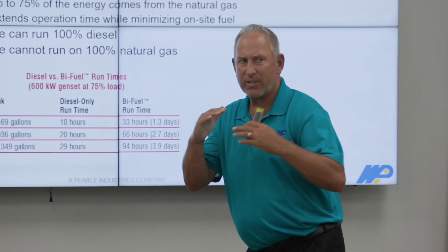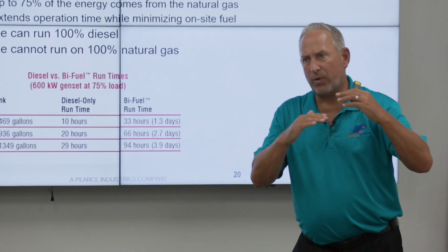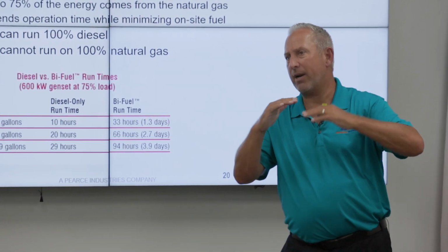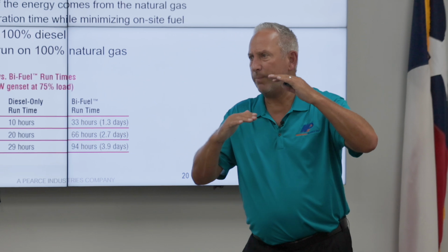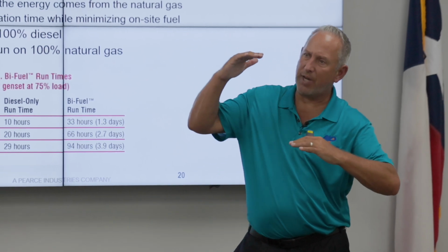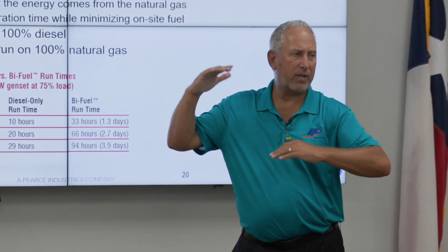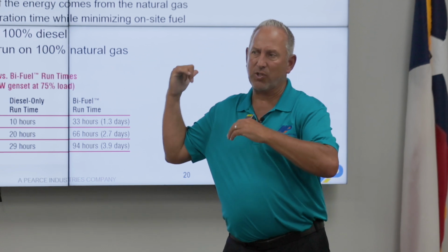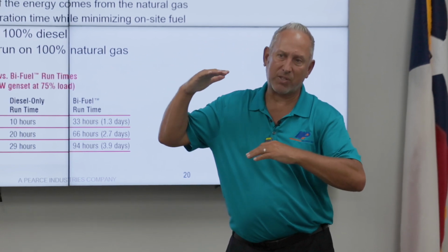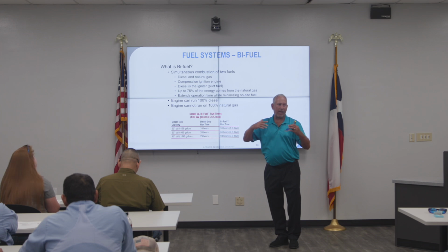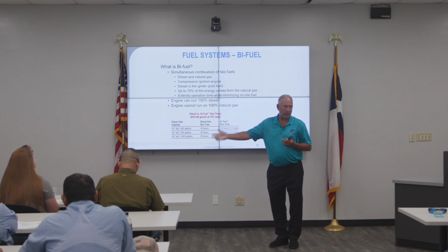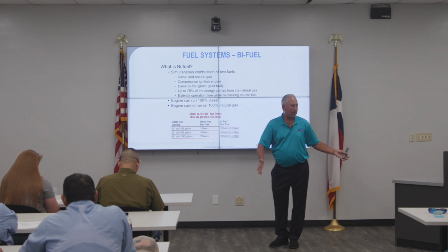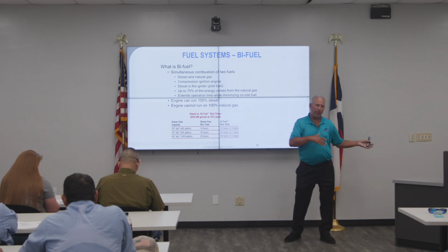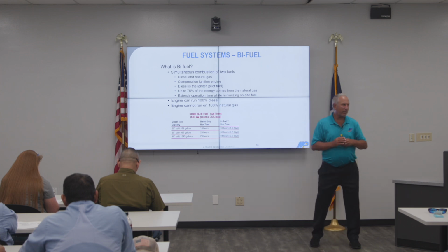Now, when you start running more on natural gas and less on diesel, your particulate matter goes down, but because you're doing natural gas, your NOx goes up. So what Generac does is they put a catalyst in the exhaust of a bi-fuel unit to combat the NOx. But at the end of the day, the EPA considers them to be a diesel engine, because if you don't have natural gas, you can run on diesel. Now, it can't be the other way around -- no diesel fuel, you've lost everything.